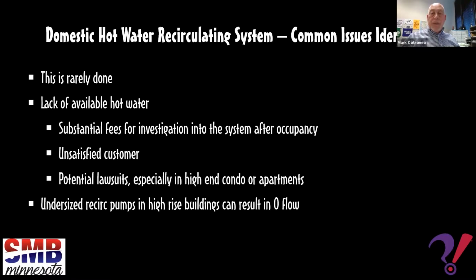Also, a lot of the TAB companies will shy away from plugging into the domestic recirculating balancing valves because of the potential risk of contamination of the system. We mitigate that by using a dedicated water meter for the domestic system, which is disinfected prior or after each use. You could also use an ultrasonic water meter, which doesn't plug into the valves themselves, but measures the flow through a pipe, which again, you're not plugging into the valve, so you're not taking that risk on.